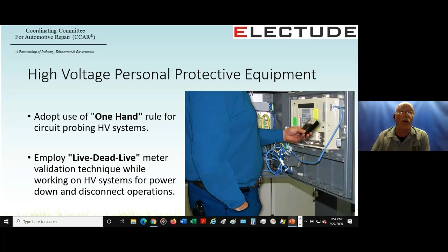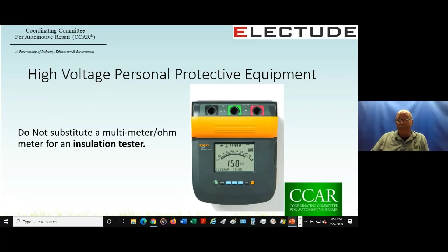If you can see the image, this particular Fluke meter is showing 150 gigaohms, but the reference voltage is 5,249 volts. Insulation testers are different animals compared to a multimeter. There's no way a traditional multimeter can give you a reference voltage of 500 to 15,000 volts.